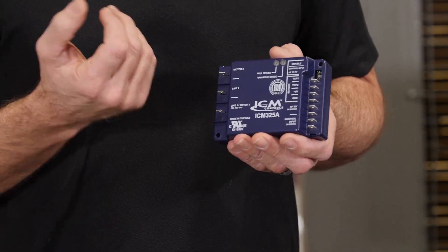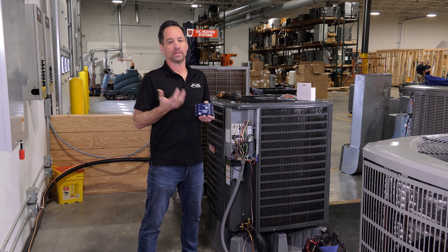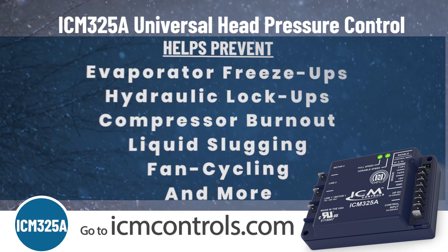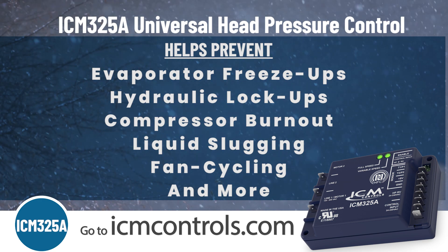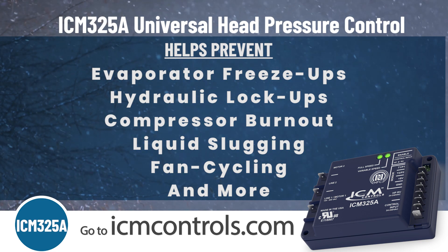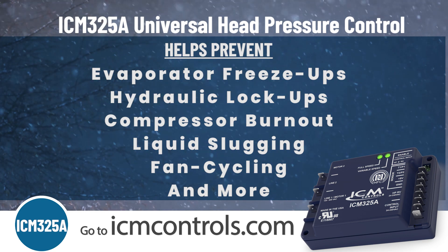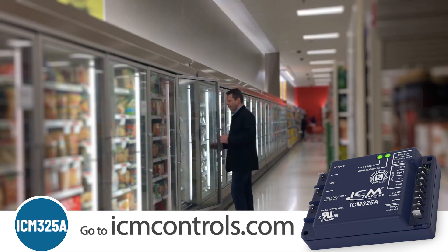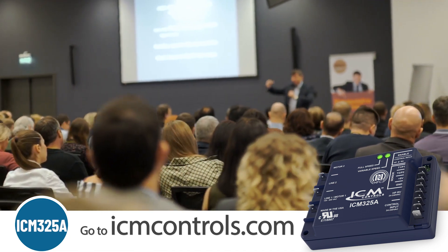Today we're going to talk about some of the applications for the ICM325A, where you would use it, and how to install it in low ambient conditions. Cold weather conditions could cause costly damage to your HVAC systems. The ICM325A could help prevent evaporator freeze-ups, hydraulic lockups, compressor burnout, liquid slugging, fan cycling, and more. Some common applications where you might need air conditioning in the winter would be a doctor's or dentist's office, refrigeration systems, server rooms, or spaces for large gatherings, just to name a few.